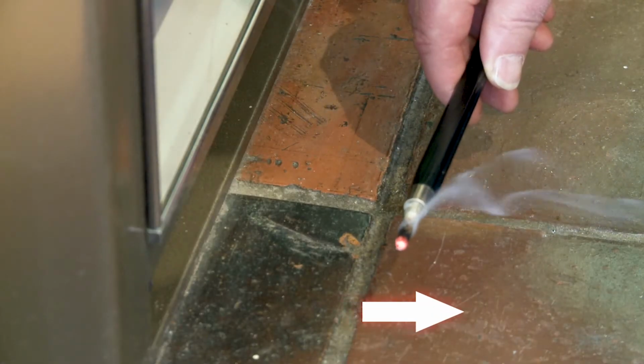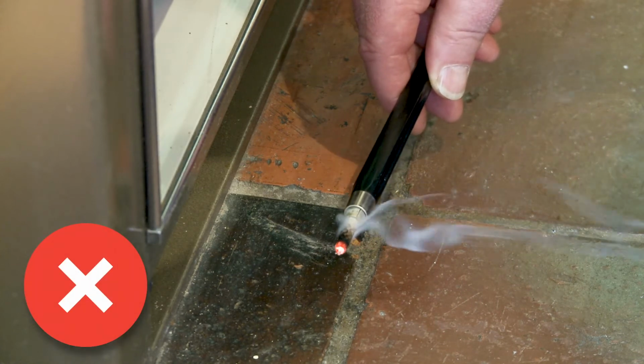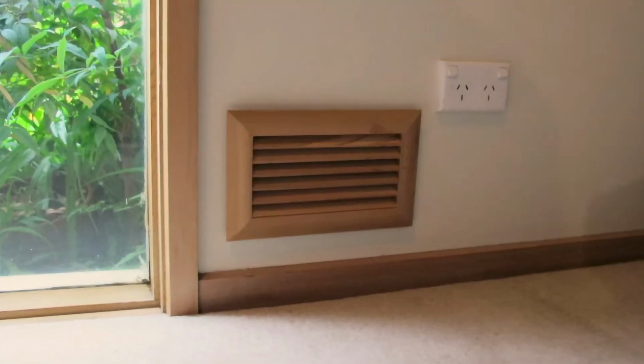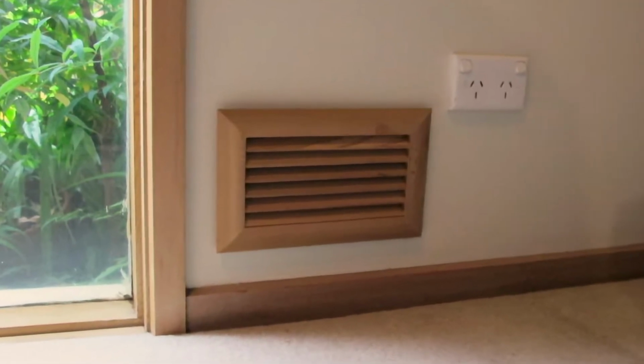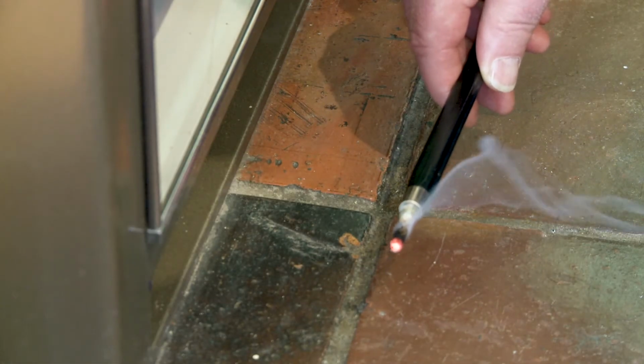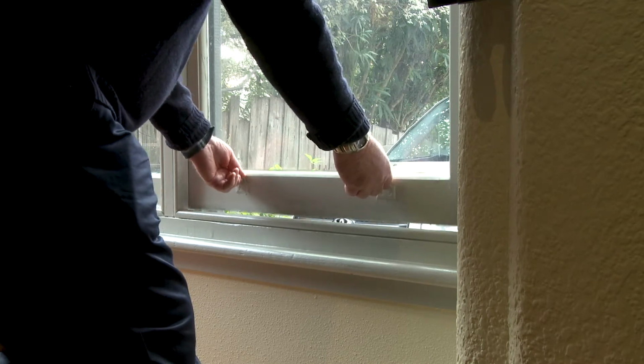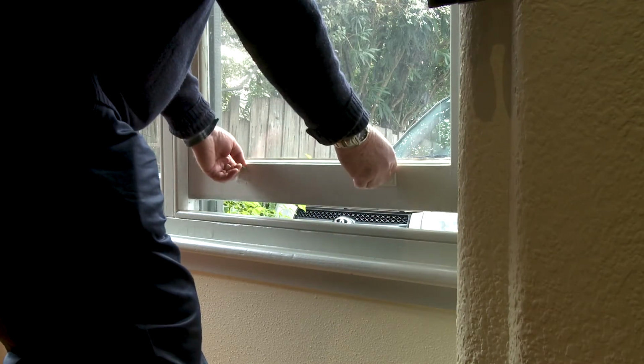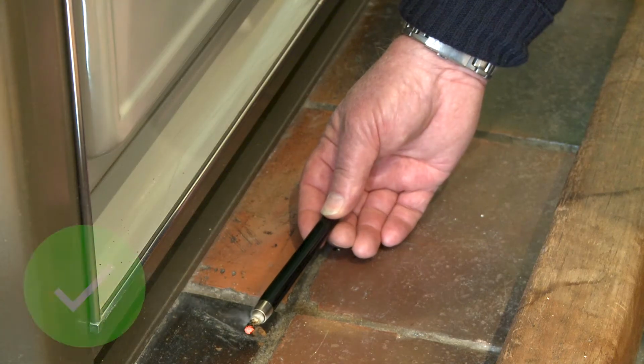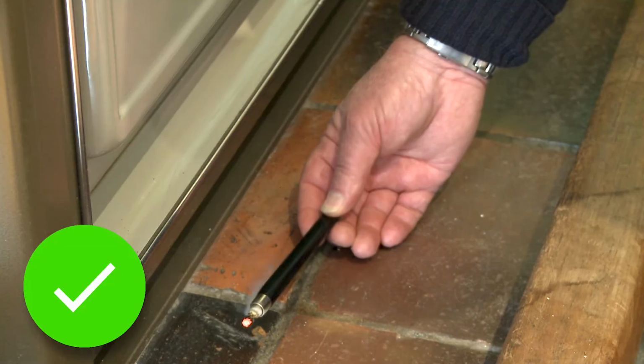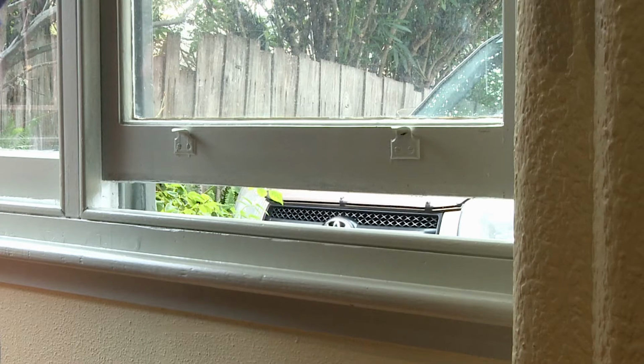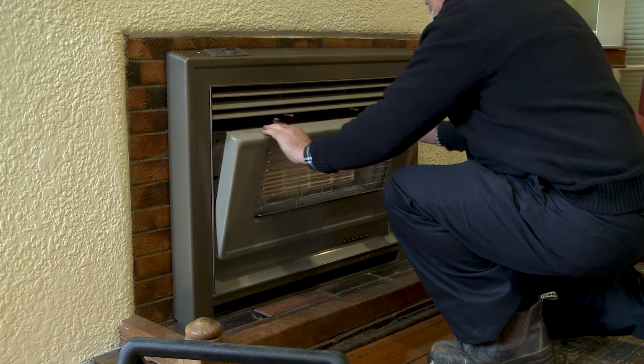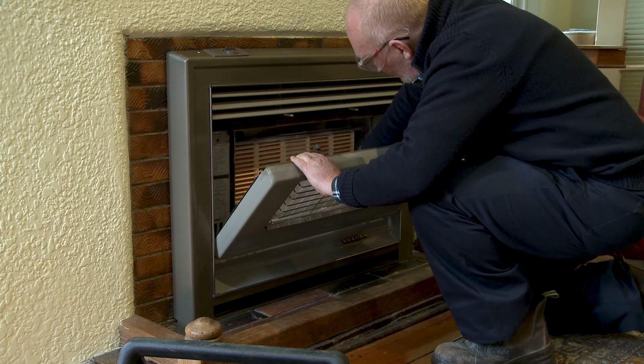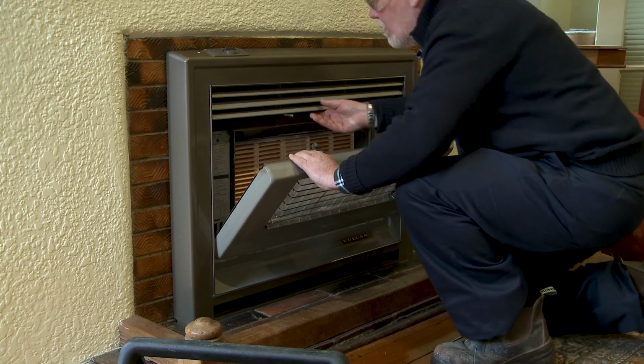If smoke is drawn away from the appliance, then you have a negative pressure situation requiring the installation of additional permanent ventilation. While continuing the smoke test, progressively open a window in the room where the appliance is installed until the smoke is no longer drawn away, meaning you've cancelled the negative pressure situation. The size of the window opening will also indicate the size of the additional permanent ventilation you need to install to make the appliance safe. The appliance should be serviced and cleaned at this stage prior to commencing the spillage test.